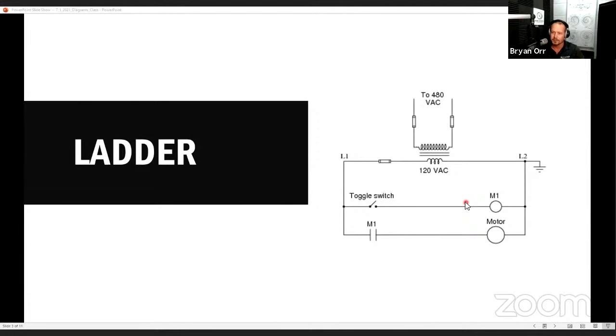You're going to see some series circuits, but in general, a series circuit is referring specifically to loads in series, not switches in series. A lot of people will say, daisy chain switches together, like in a safety circuit. That may be a series of switches, but that is not a series circuit.